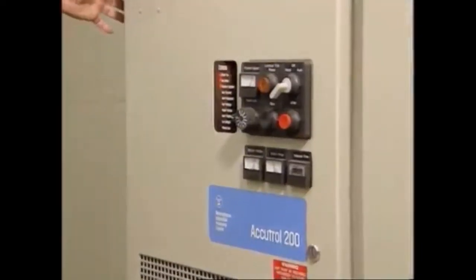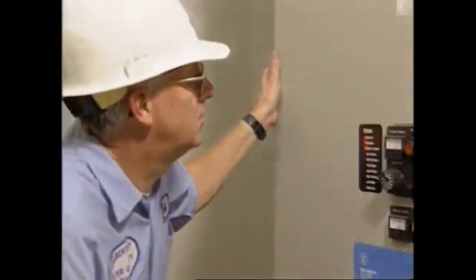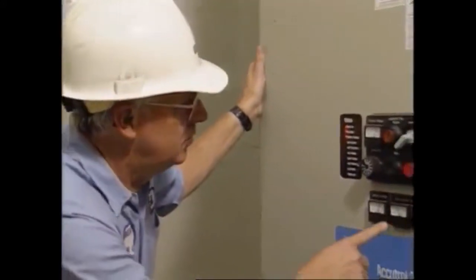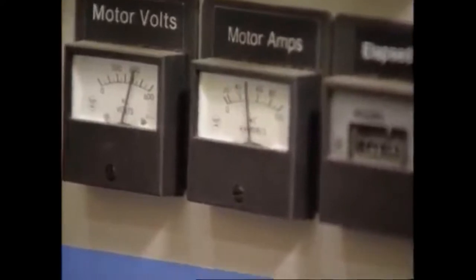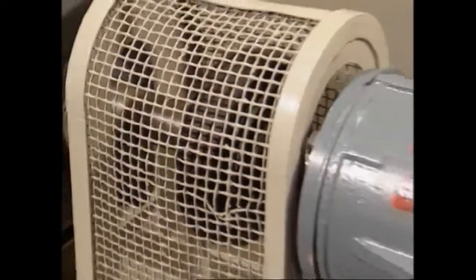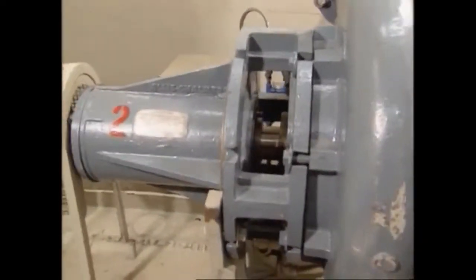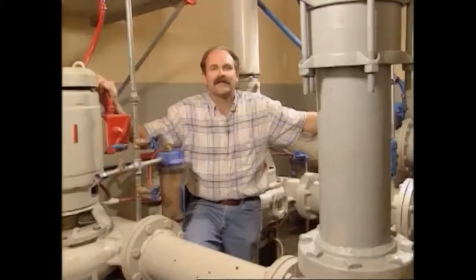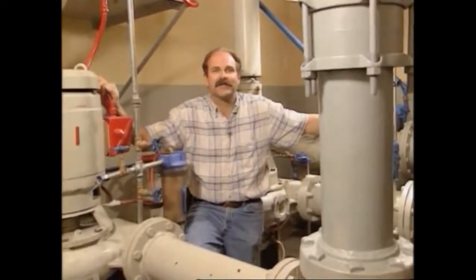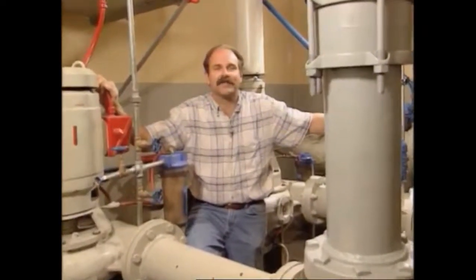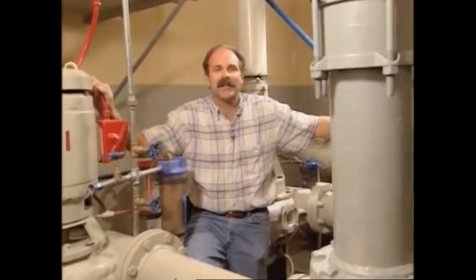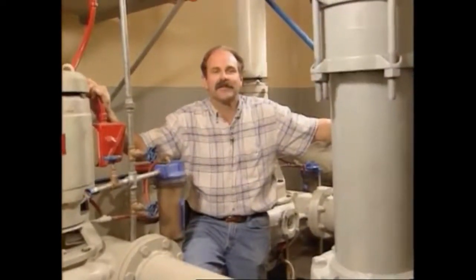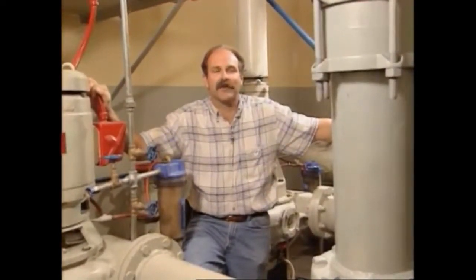Heat is also generated each time a motor is started. The current required to start a motor is often 5 to 8 times as much as the current used to run the motor. Therefore, frequent stops and starts of the motor shorten its life. With short cycling or excessive starts, the generated heat never has a chance to dissipate. One solution would be to install a reduced voltage method of starting the motor, or change the operating procedures to reduce the start and stop frequency.